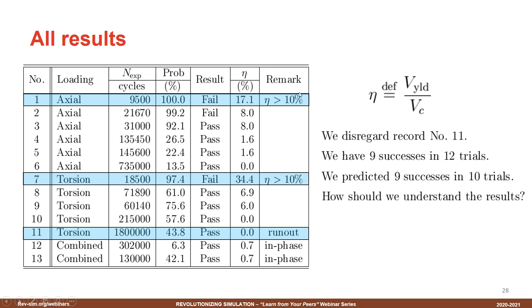So let's analyze the validation data. We said that we predicted 9 out of 10 specimens to be successful in a validation test. Instead, we had 9 out of 12. So let's see, what does it mean, 9 out of 12 and 9 out of 10? Well, this one is a very fundamental statistical result, and that is that the probability of n successes in M trials is given by the binomial distribution. The binomial distribution is the formula in front of you, where theta is the ratio of the successes to the total number of trials. In this case, it would be 0.9 because we predicted 9 out of 10. In validation, however, we're interested in the inverse problem.